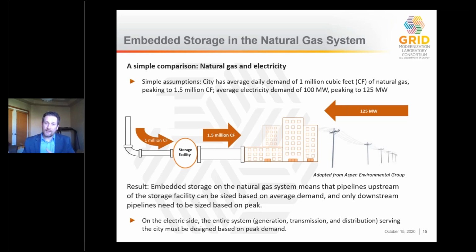But contrast that with the electric side, we don't have that flexibility. If our peak demand is 125 megawatts, we have to design the entire system, generation, transmission, distribution, to meet that 125 megawatt demand. Even if we're only in that peak condition for a few hours of a year, the entire system has to be sized to meet it. So the value is that where we have embedded storage on the natural gas system, we can more optimally design it, reduce system costs, and have efficiencies that we don't have available to us on the electric side now. Next slide.